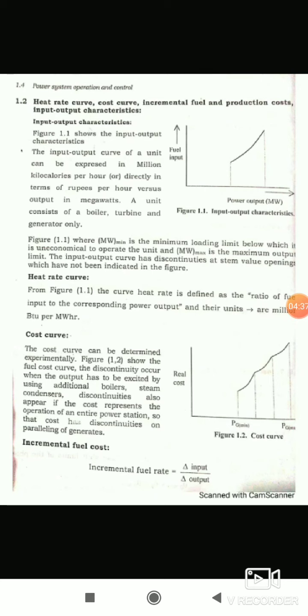Next, heat rate curve. The heat rate curve is defined as the ratio of fuel input to the corresponding power output. Its units are million BTU, British thermal unit, per megawatt hour. Next, cost curve. The cost curve can be determined experimentally.